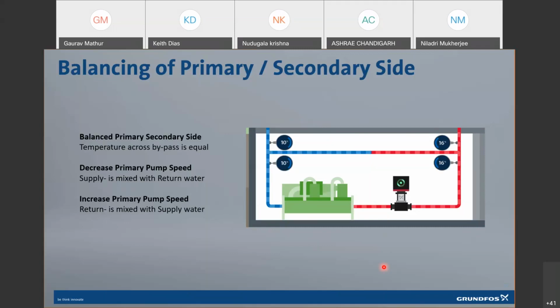The second control point which I wanted to discuss, and we have briefly discussed when we were looking at the benefits of distributed pumping, is the control of the primary chilled water pump. You have already seen that the primary chilled water pump size has been reduced. And now you have 4 temperature sensors across the decoupler. So it's a traditional decoupler. Now what you are seeing is a change. When you talk about variable primary, we have always spoken about going for a flow control valve or a bypass valve or a minimum flow bypass valve. But here you are going for a variable primary and a variable secondary side without a flow control bypass valve.